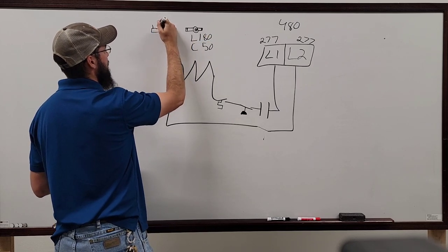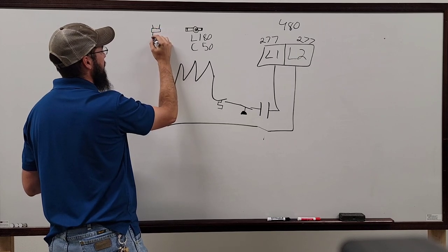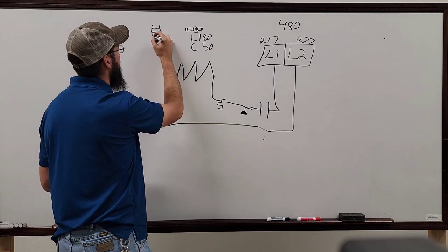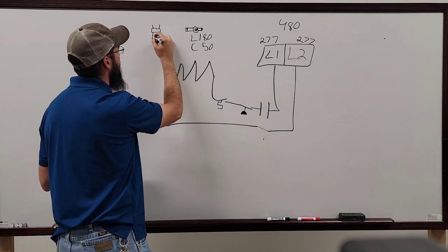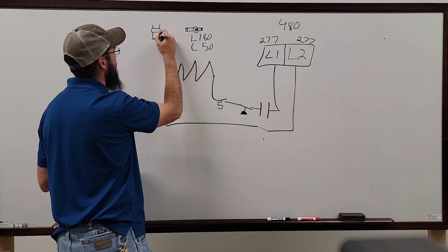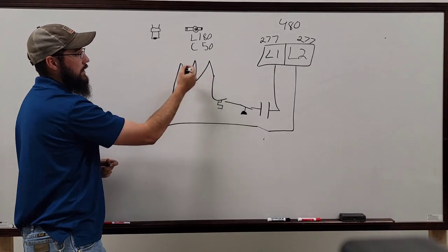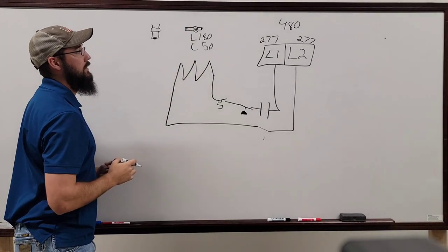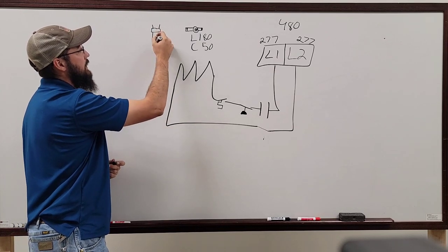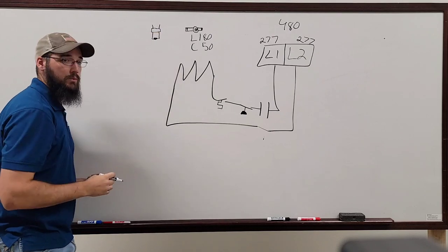You're going to have a ceramic disc with two spades, and it's going to come down here. The old school techs called these teardrop limits, because it literally looked like a little teardrop. Here's your little fuse coming back. And this would sit in the same place as the bimetal limit. The difference is, these bimetals will reset, these fusible links will not.